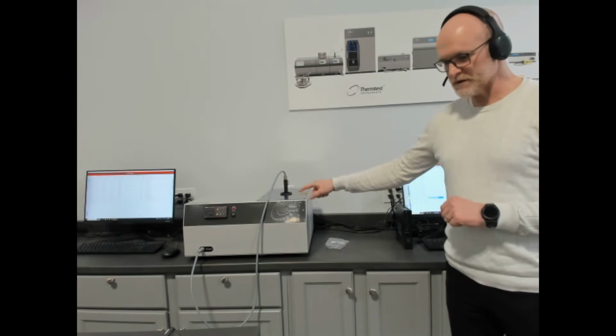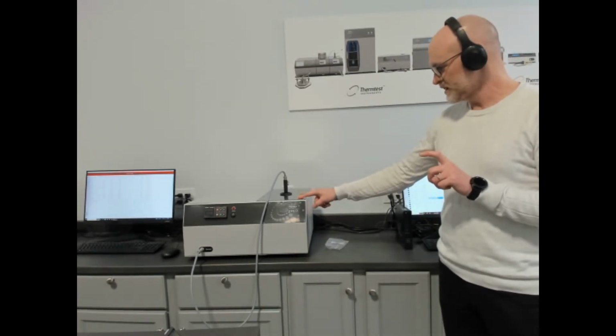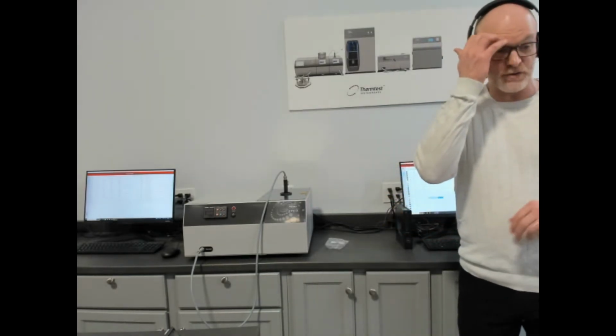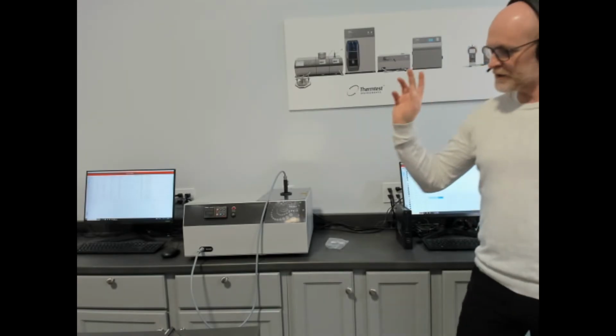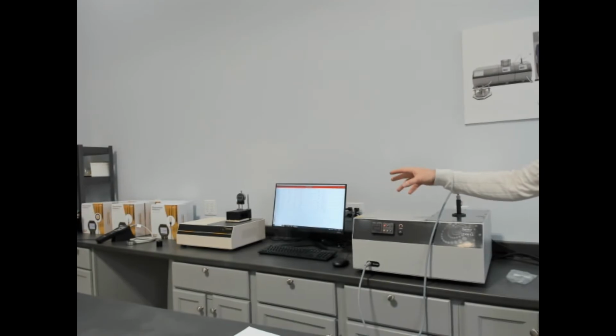The key parameter of this method is the way it measures conductivity with a wire. In addition, you can back pressure the cell to allow you to test past boiling points. Controlling convection is key.